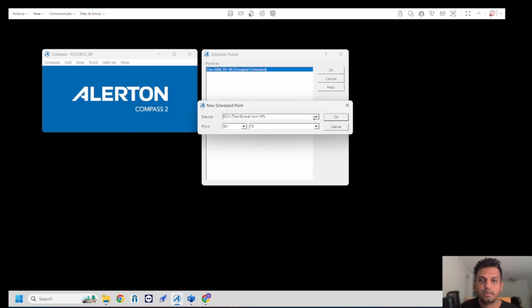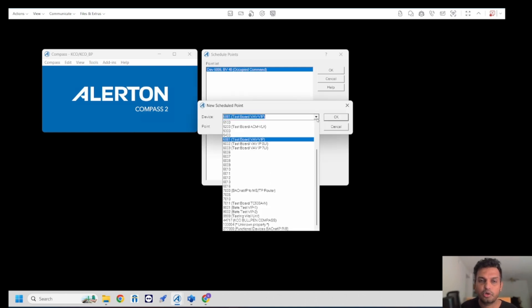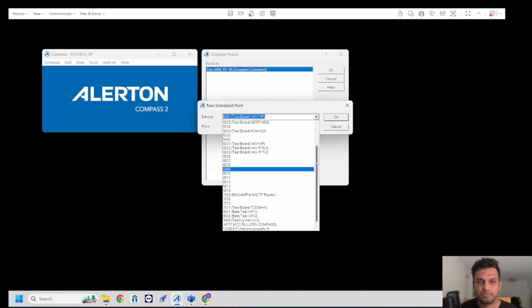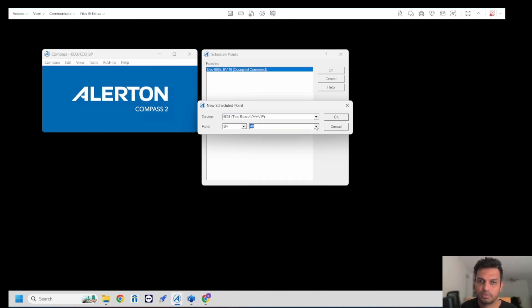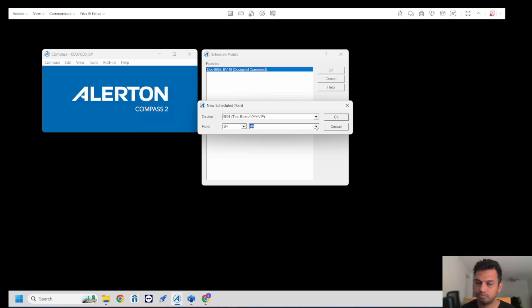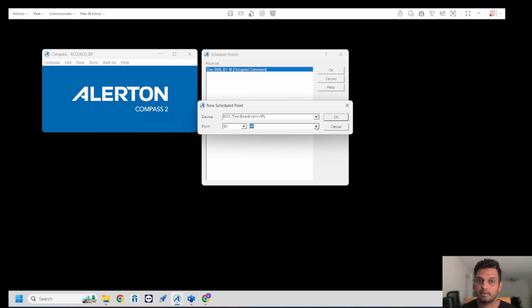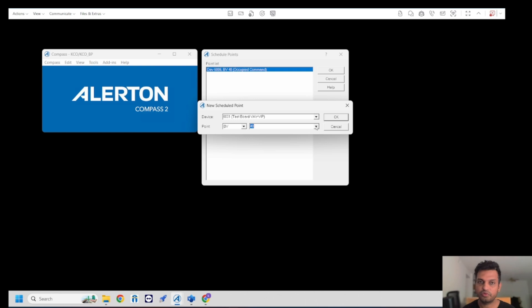Once this screen pops up, you click on the add button and from the dropdown you have to specify that particular area or controller. Currently I'm going to choose a VIP controller. Then my point becomes a binary value and my object instance becomes BV40. If you're working on Alerton you know why you've got to use BV40 because it has a specific standard that Alerton has made under BV40.